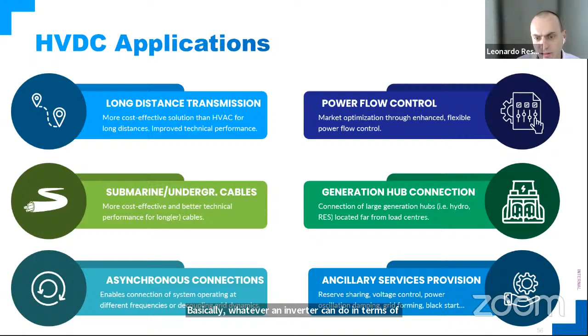Something that can come as a byproduct of HVDC together with transmission capacity is the ability to provide ancillary services - reserve sharing, voltage control, power oscillation damping, grid forming, black starting, and many others. Basically, whatever an inverter can do in terms of ancillary or grid service provision, we can do with HVDC as well.